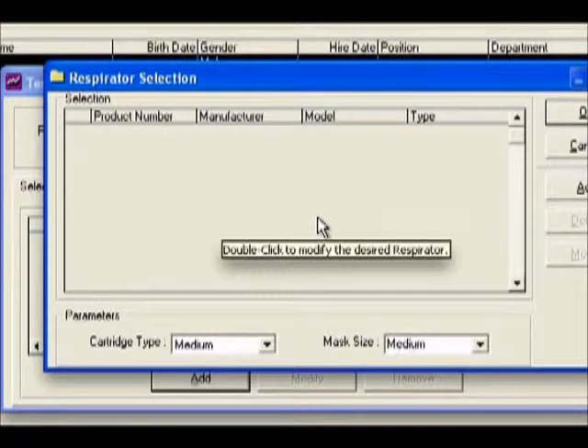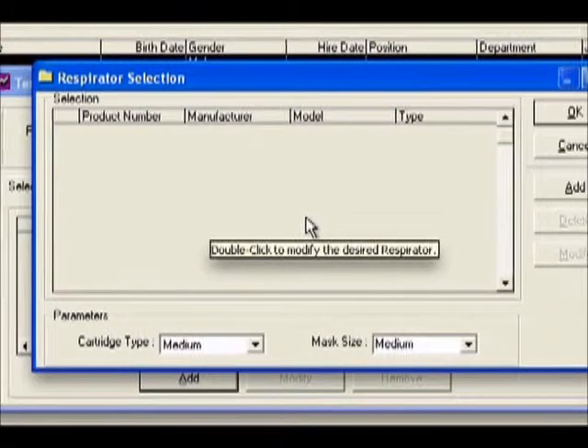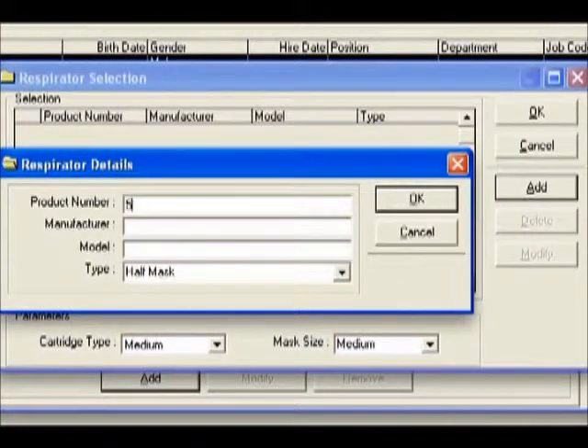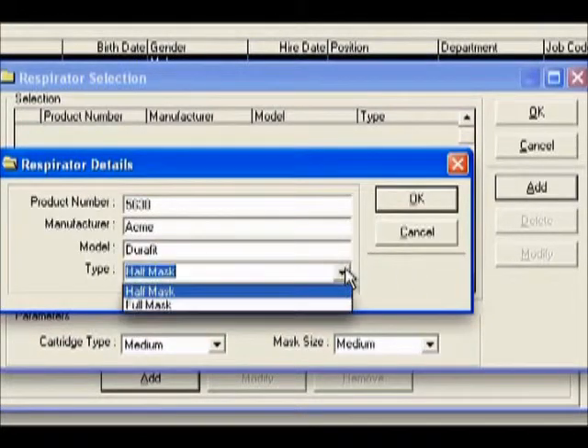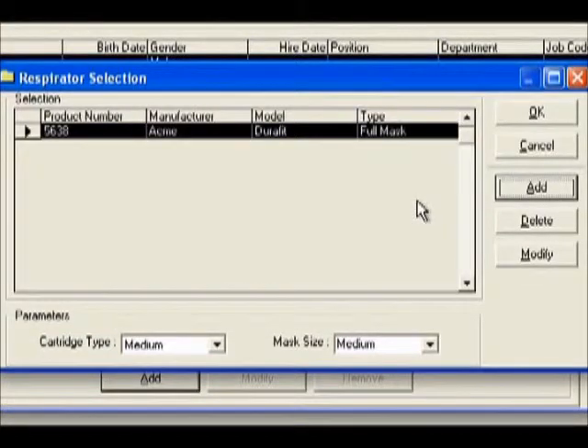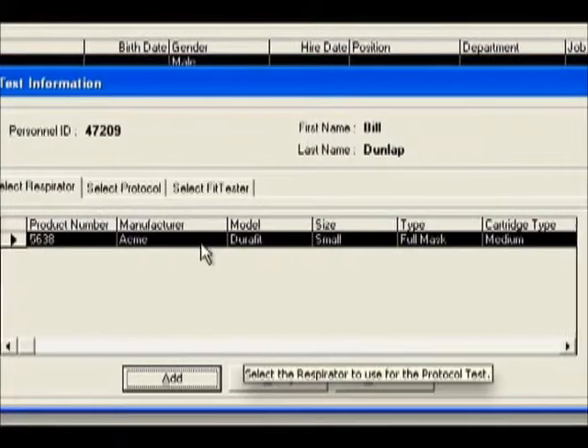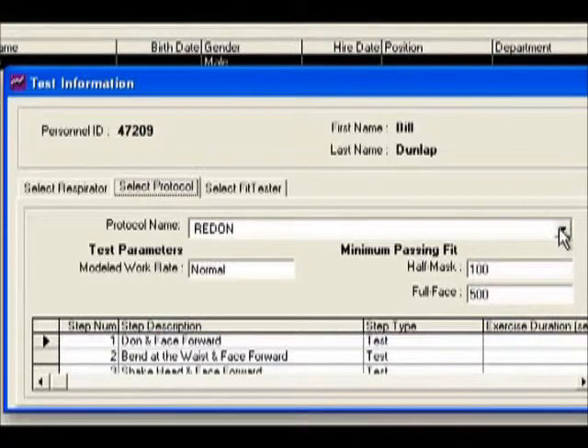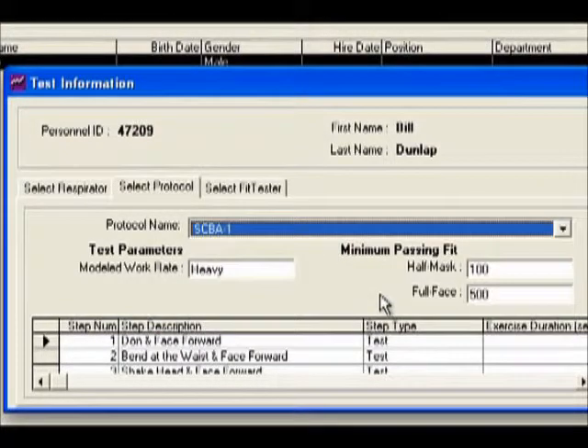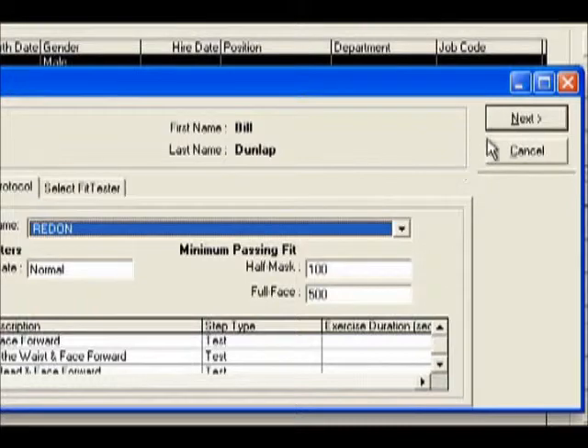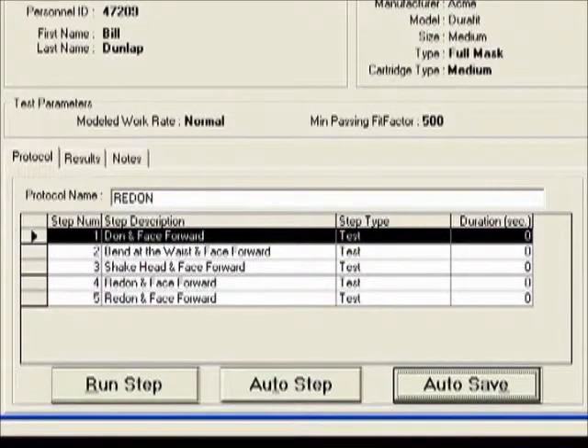The first time you enter this screen, you must add a respirator to your selection list. Click the Add button on the right side of the window. Fill in the appropriate information for the respirator you wish to use. If you are using numerous brands of masks, enter each one in this section. Click on the middle Protocol tab to select the protocol you would like to use for this test. The protocol you select will become the default protocol on future tests until you change the protocol selection again. When finished, click Next. You are now ready to perform a fit test.